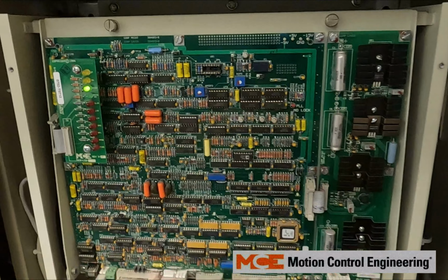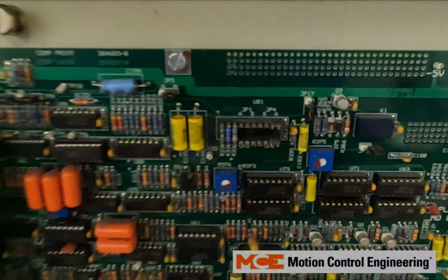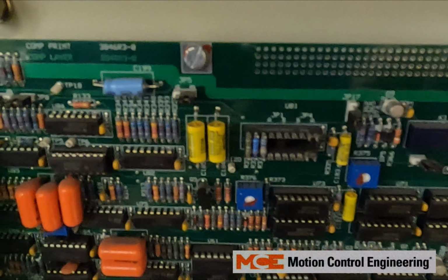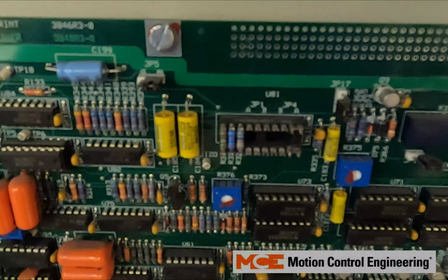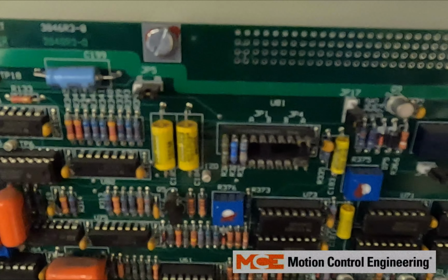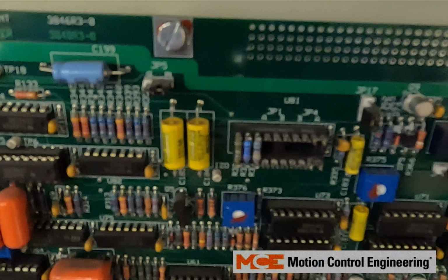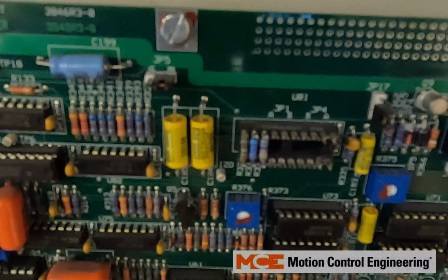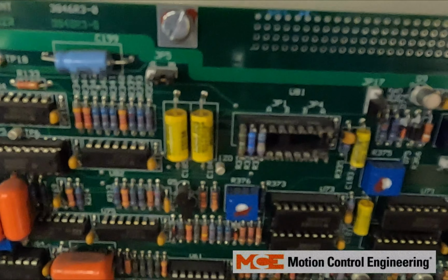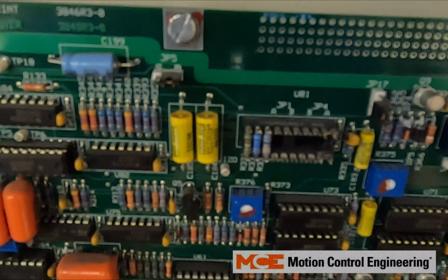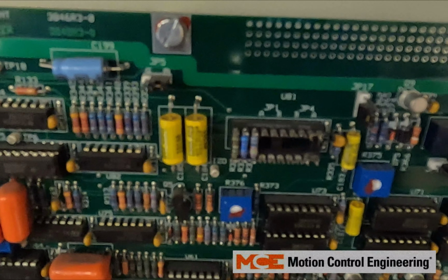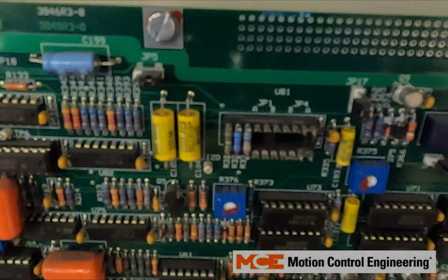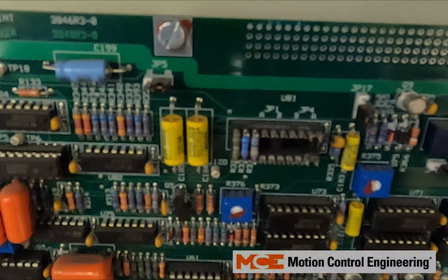So we're going to take the drive cover off. We're going to look at your drive header chip on your SCR-LGA board, and look at the ratings. This is an HDR 2407, indicating that it's 240 volts, and the 7 is a 75 amp output rating for 100%.